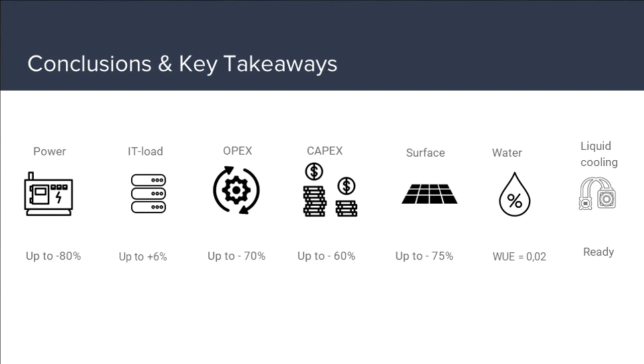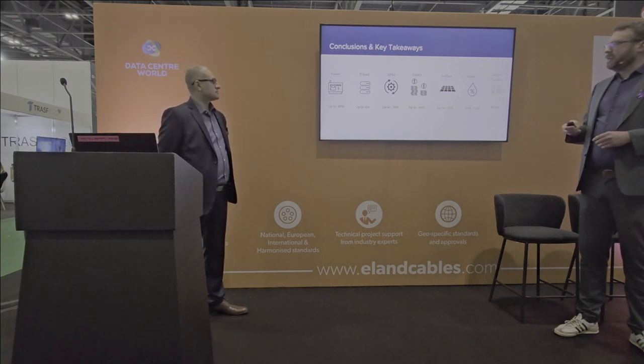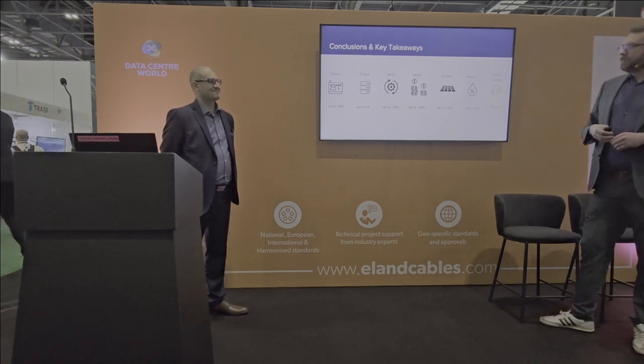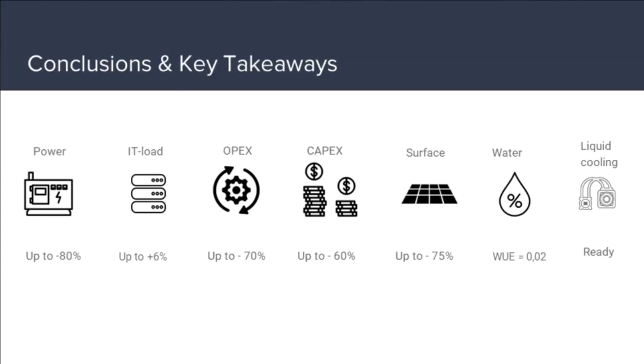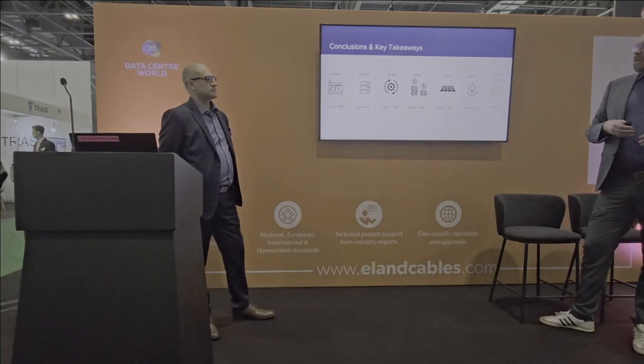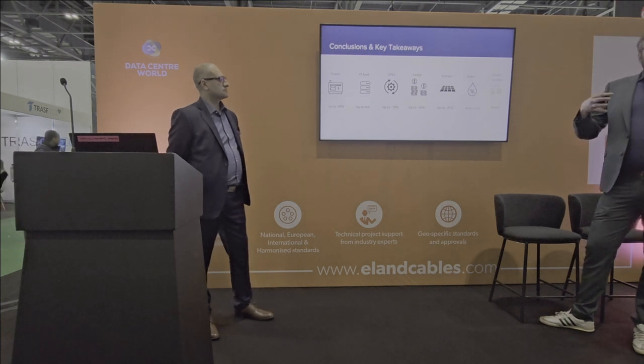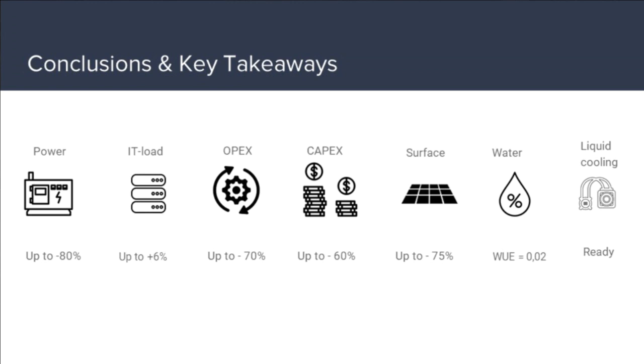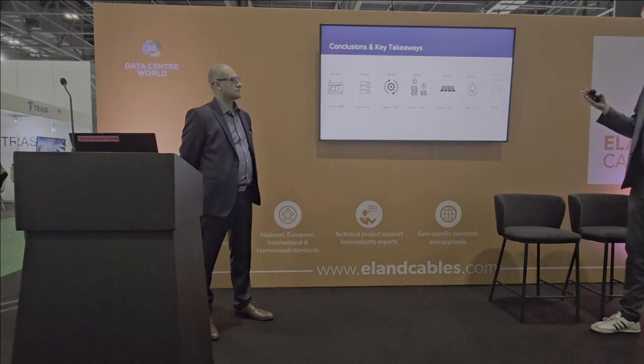So to put this all together, we believe there is a way to integrate those data centers. We just threw up a little bit of KPIs that we can think about when going to those really high density, really high load racks. The total power we see down up to 80%. The IT load, we can incorporate more IT load in this. The overall OPEX of this solution with the microgrid and the adiabatic cooler can be 70% lower. We have CapEx advantage of up to 60%. We lose a lot less surface for those large data centers that nowadays. And we have an extremely low water usage. Adiabatic is seen as evil, but we found a way to still make it work when it's applicable and it's liquid cooling ready.